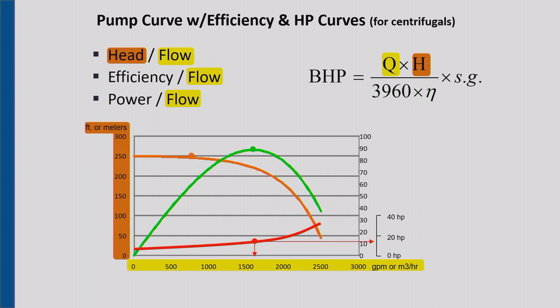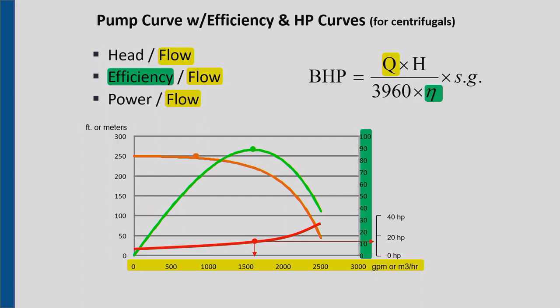Okay? So, in addition to that, I've also got efficiency. Efficiency is the green curve, 0 to 100% efficient. Here's the efficiency in the pump formula. And this green line is the efficiency versus flow. If I've got that discharge closed down and I'm not pumping anything at all, I'm putting energy in and I'm getting nothing out, what's my efficiency? 0. Nothing's coming out. I'm not doing any work.